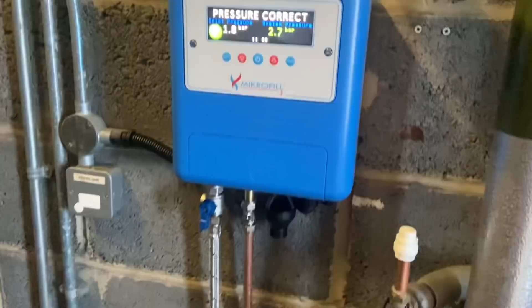Here we can see on the left we've got the inlet pressure, and here's the system pressure. Yes, it's slightly high because we haven't vented round yet, but we're just looking at this inlet pressure, and it's bouncing between 1.2, 1.3 bar all the way up to 3 bar.